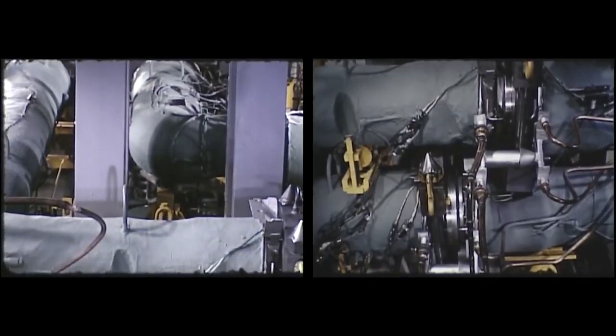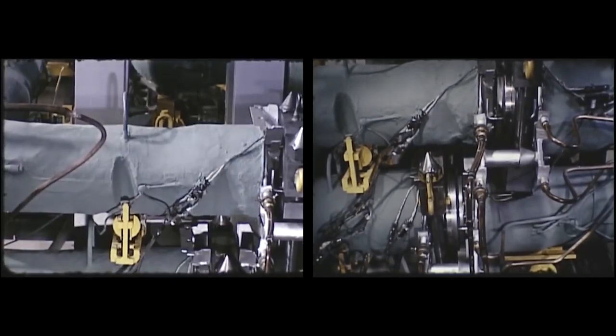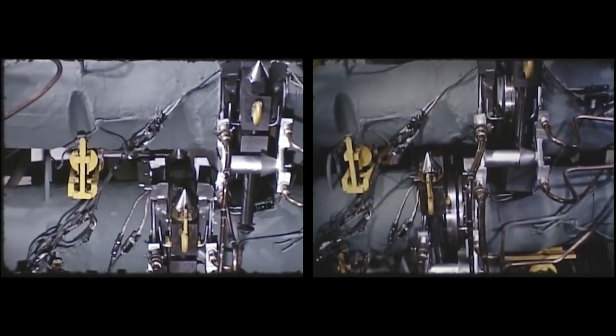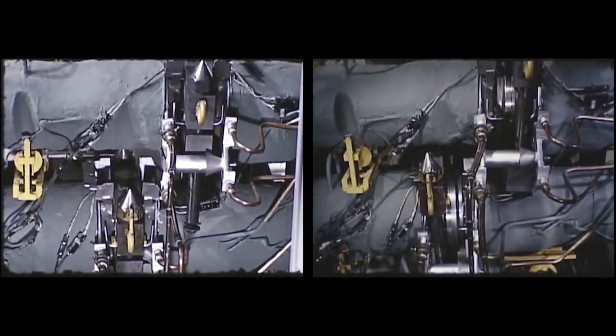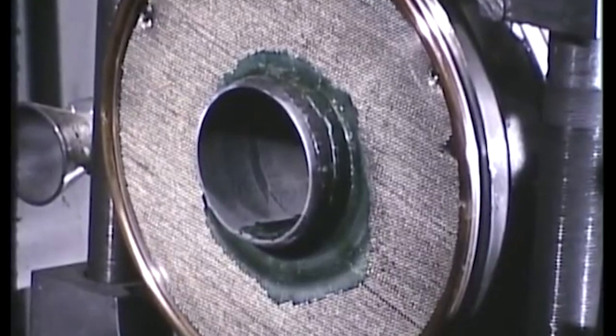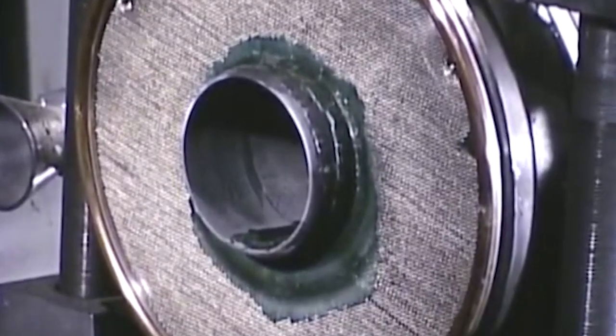To remove and replace the component, it must be possible to break and remake pipe connections to extremely leak-tight specifications. A freeze flange is used. Such a joint takes advantage of fused salt properties to form a frozen seal between flange faces.